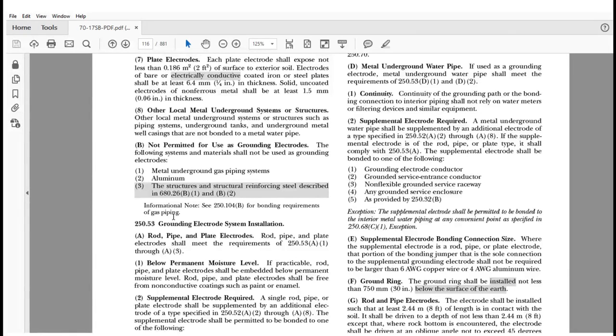But in this case, Code Making Panel 5 determined that it was never the intent of the NEC to use anything to do with the bonding grid as a grounding electrode. That was discussed during Code Making Panel 5's discussion during the development of this section change. Incidentally, I will note that this is a totally new application that was added, which is item 3 of 250.52(B). So look that over. I don't know of anybody that did this application, but in case you did, you are no longer going to be able to do it.